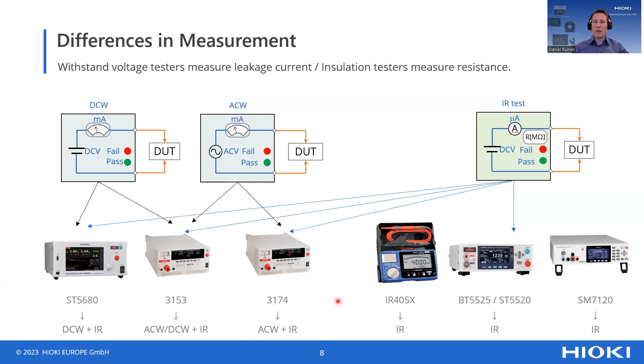In regards to application selection guide, when to choose which device, again, as a reference, the insulation resistance test is being done on cell level. The insulation resistance is the main feature. It's happening at a different level of voltage, so 500 volt for the BT5525 and 1 kilovolt for the ST5520, and the resistance value is the main interesting point. While when we look at super megohmmeter, also resistance value is very important, but on a higher resolution or higher display range, because we are testing components, and these components have a different resistance value to be measured, and also we can apply a much higher voltage here.